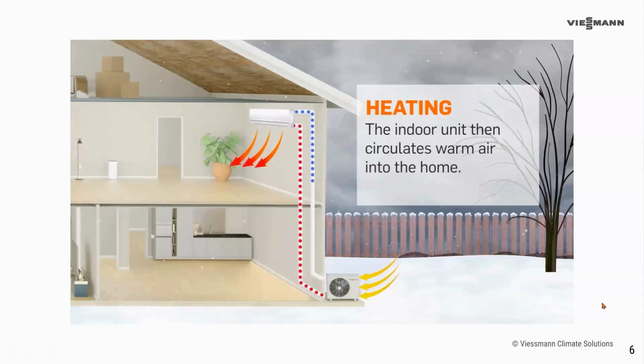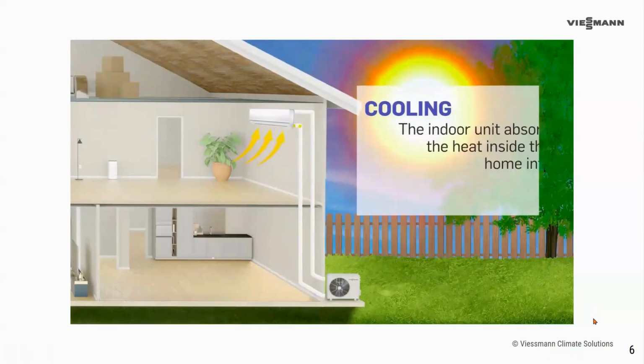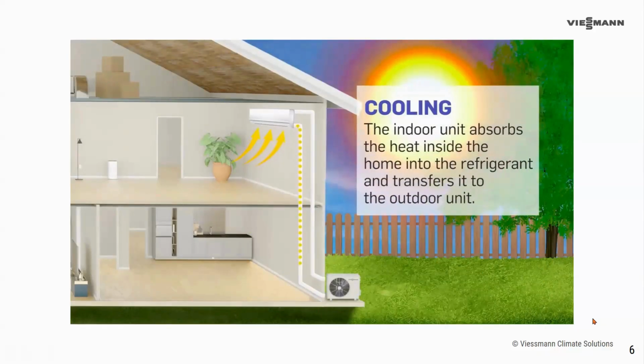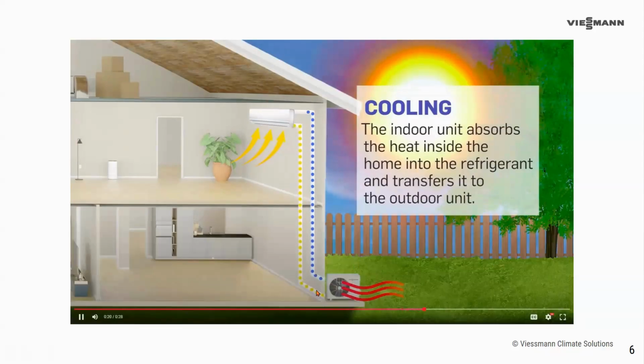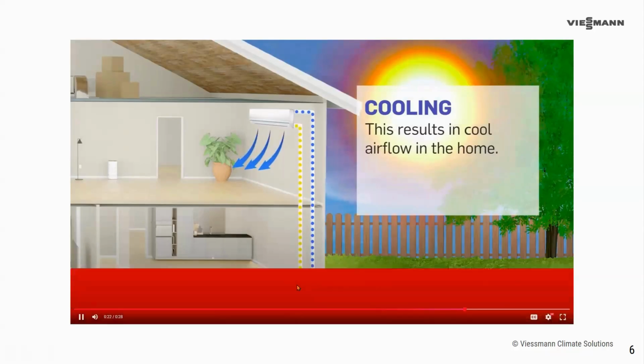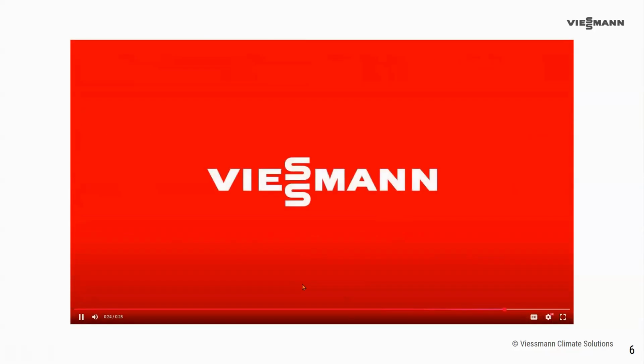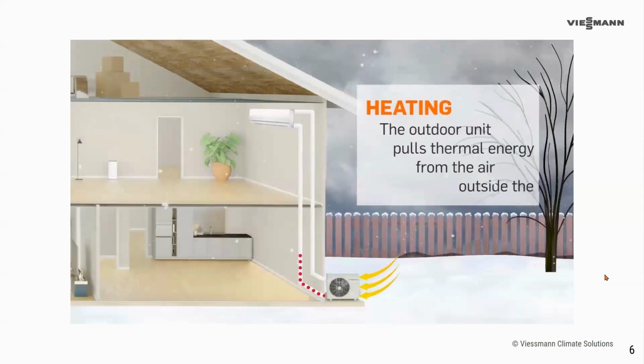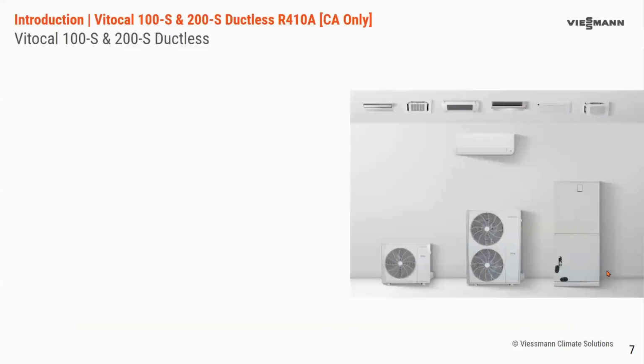Ductless, as they call mini splits. This is an air-to-air heat pump. So in heating operation, it takes the heat from the outdoor air and brings it indoors. And in cooling operation, it does the reverse. It takes the heat from the indoors and brings it outside. This is very similar to our air-to-water heat pump product that we launched late last year, or early last year, I'm sorry. The difference being this is air-to-air. This is not a hydronic system. So like Viessmann is known for hydronics, this is an air-to-air heat pump product.